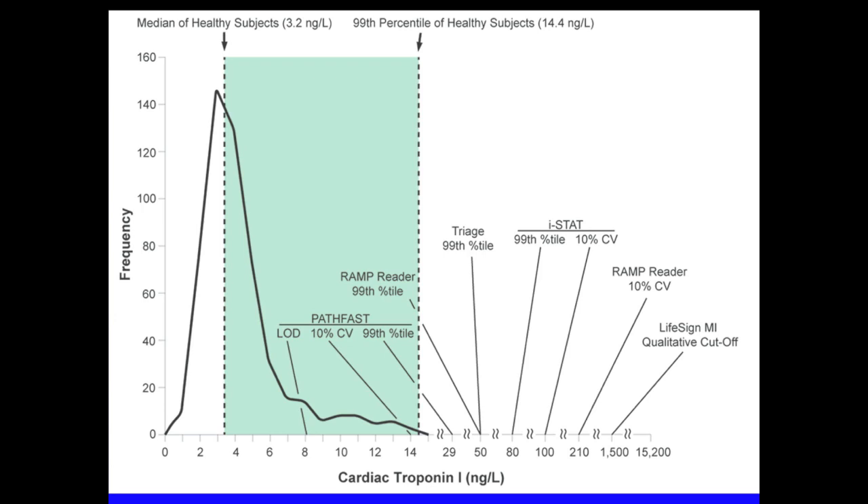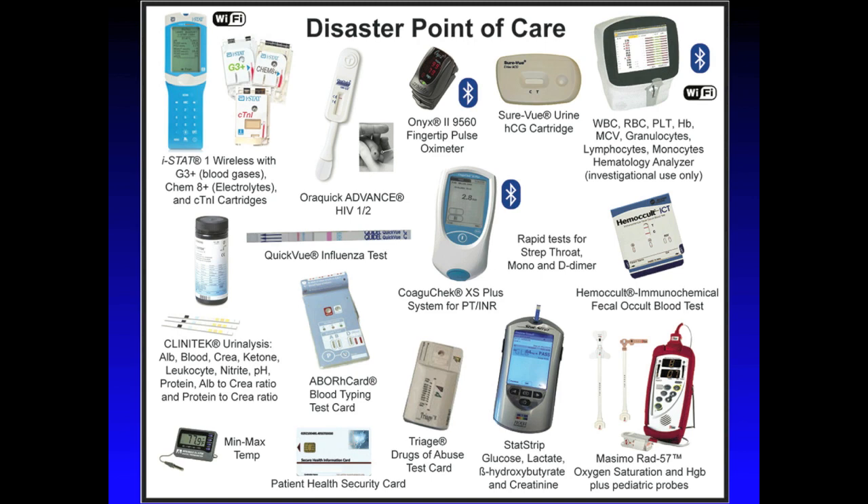This means any patient with a troponin I level above the 99th percentile is a patient that potentially has a myocardial infarction. As you can see, the 99th percentile of the normal population sits at 14.4 nanograms per liter. Only the PATHFAST comes close to meeting all three criteria, and it is even more accurate than some laboratory devices used in hospitals. Unfortunately, we did not choose the PATHFAST for our new recommended disaster cache due to its weight, and because a handheld point-of-care device is better suited for a disaster response team. The only handheld device that comes close to an acceptable accuracy is the i-STAT, which is relatively close to the normal population's 99th percentile. As a result, we chose the i-STAT as the troponin I testing device for our new recommended disaster point-of-care cache.